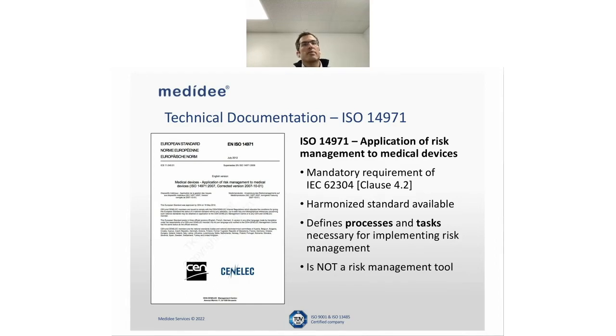ISO 14971 basically characterizes one of the key principles in medical device development, which is risk management. It gives you the framework on how, or what you have to do, to ensure that your risk management process is in place and is efficient. It's also recognized by the European Commission. That's what we call a harmonized standard. It is actually required by 62304, so you have to use it. It's an expectation, and it will define the process and the tasks that you have to implement.